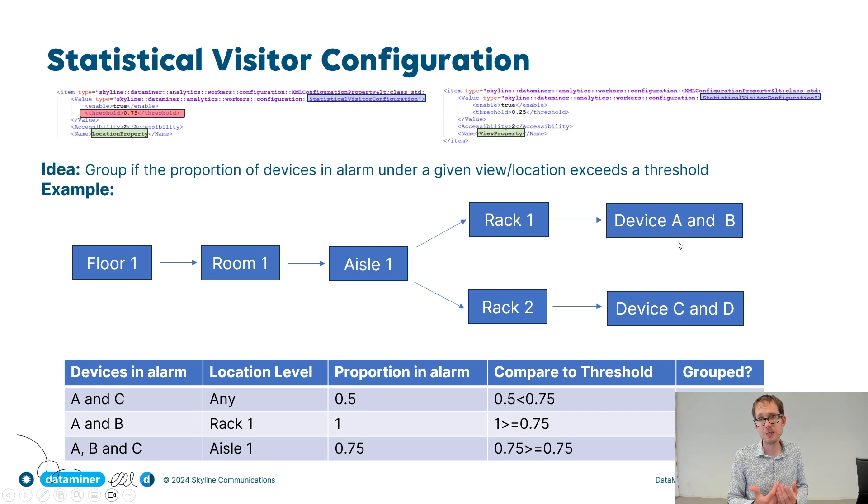Now assume first that A and C are in alarm. In that case, 50% of your devices are in alarm. But 50% is less than the configured 75%. So in this case, we will not group the alarms. On the other hand, what if there are alarms on A and B? Well, A and B both belong to rack one. So basically 100% of the devices in rack one have alarms. Now 100% is more than 75%. So yes, we will group those alarms.